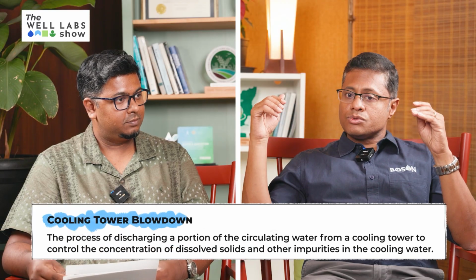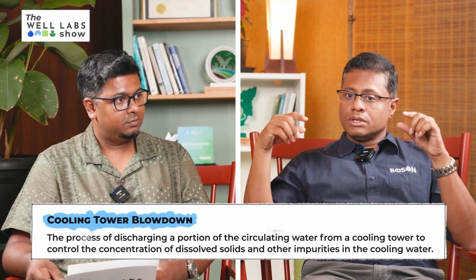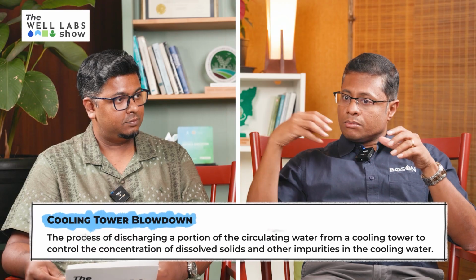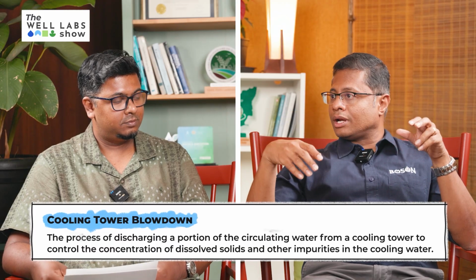Most important thing is blow down. If they use very high total dissolved salts water, based on the TDS level they blow down a portion of the water to the drain. So if they use 700 ppm TDS water, the blow down cycle could be 2 or 3 times a day. This blow down happens from the cooling tower itself, not the reverse osmosis, because the water evaporates and the salts stay back, becoming concentrated, so they have to send that water out.